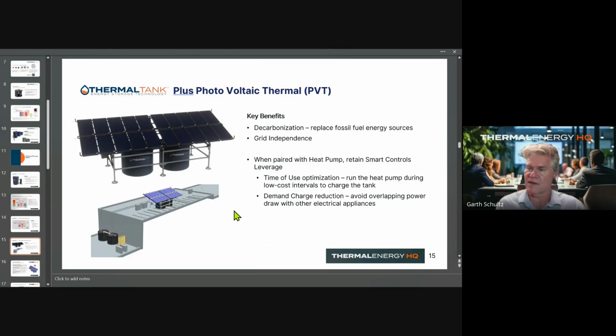On good sunny days in the Caribbean, the heat pump runs very little, and all the energy for showering cycles through the tanks associated with the heat pump without it turning on. At high demand periods, or during a series of cloudy, hurricane-type weather, the heat pump takes over and supplies that baseline energy. It's a perfect marriage of the two technologies, coupled together with our thermal storage system, maximizing storage so that at nighttime and off days of solar, the client is still supplied.